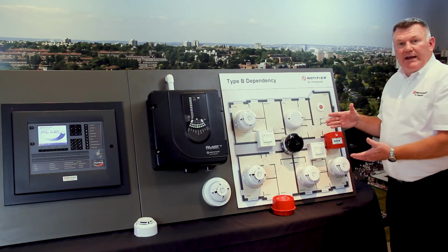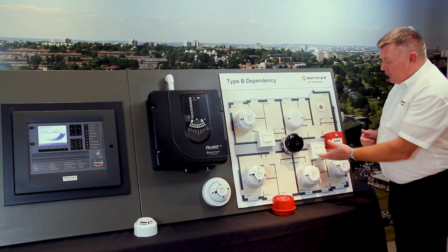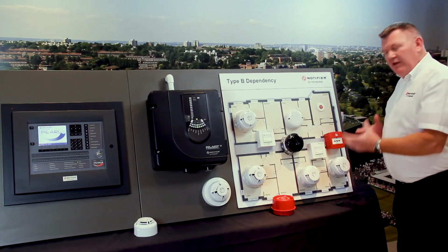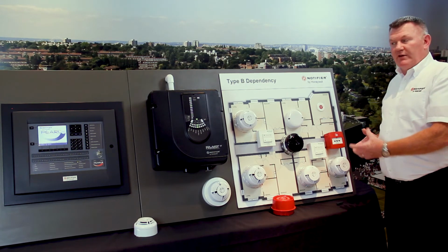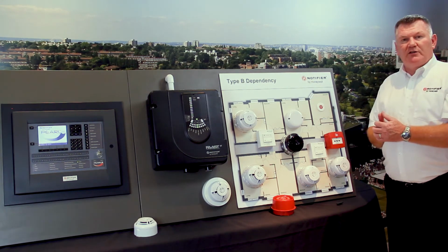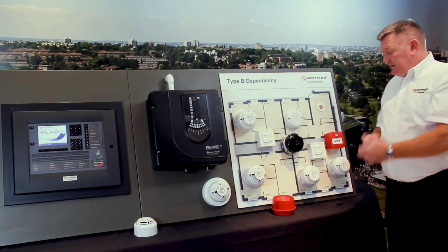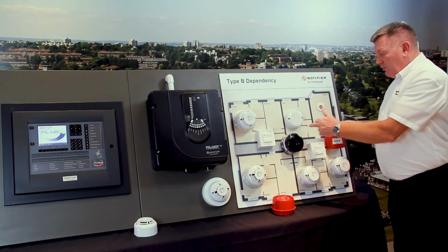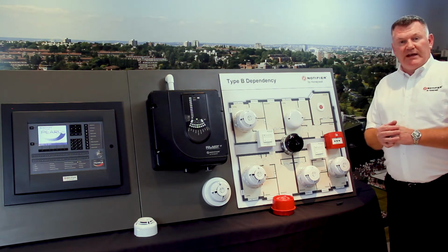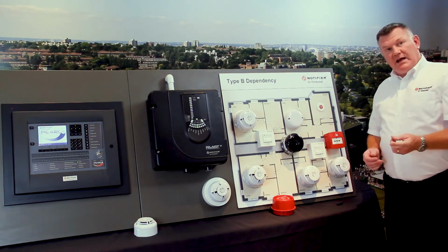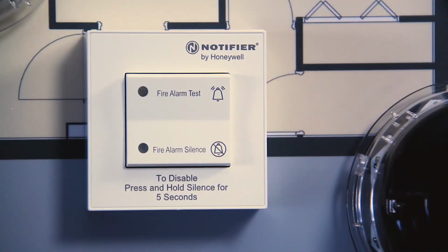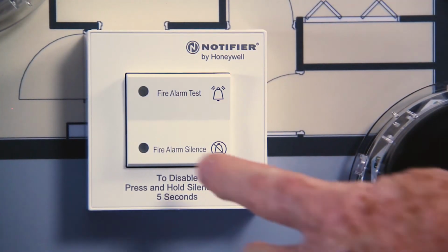So what I'm going to do now, again, in flat 4, again the local silence button, if we know we're going to burn some toast and we don't want to set the sounders off and we don't want to set an alarm condition to the fire control panel, we have the ability to disable the detectors within that zone for a period of time, set at 5 minutes on this control panel.